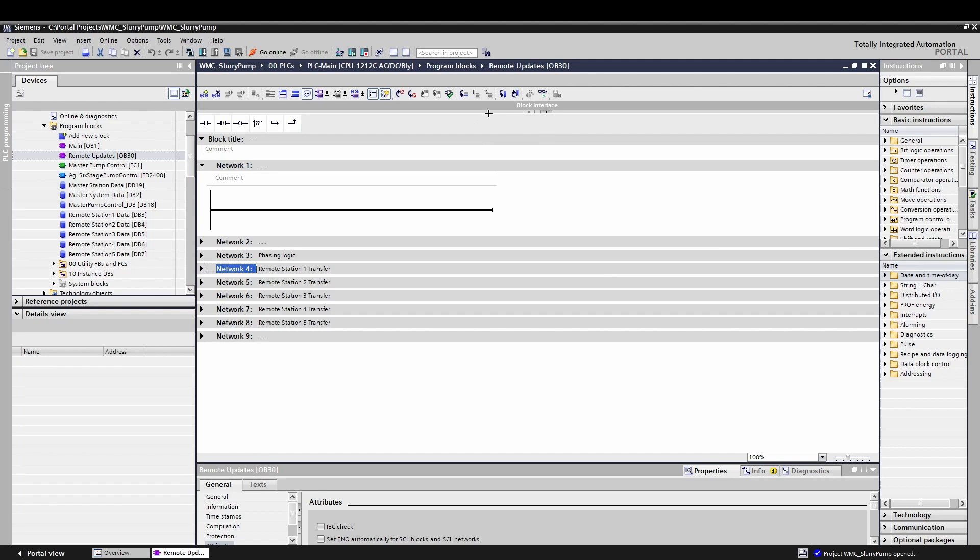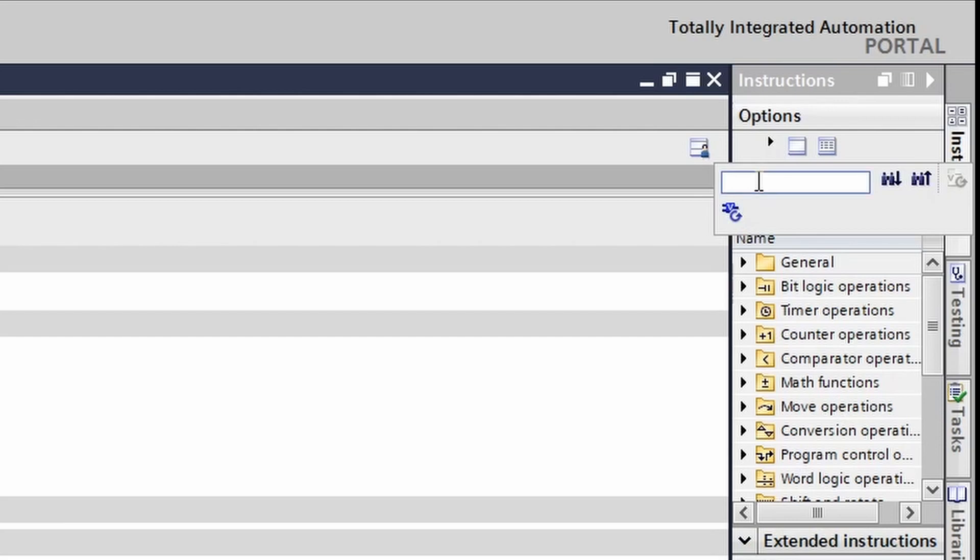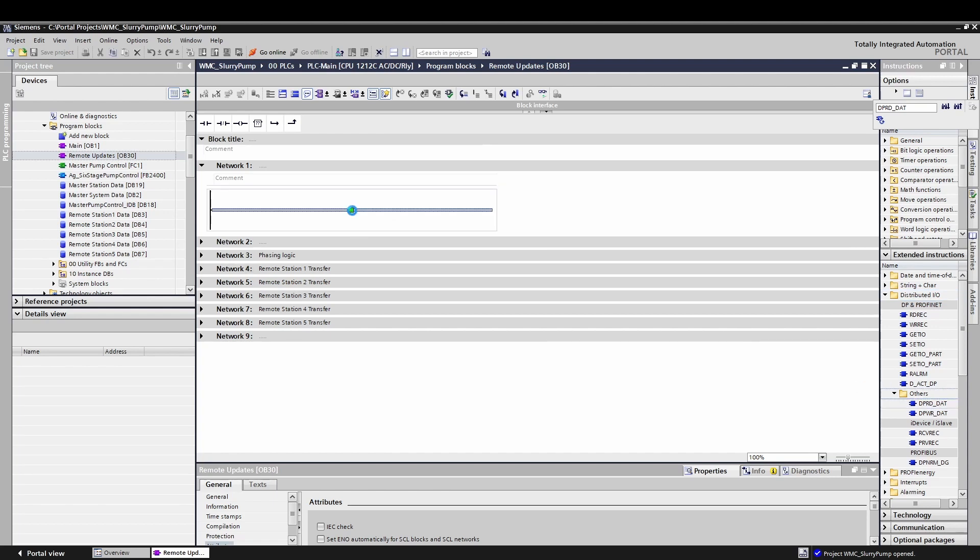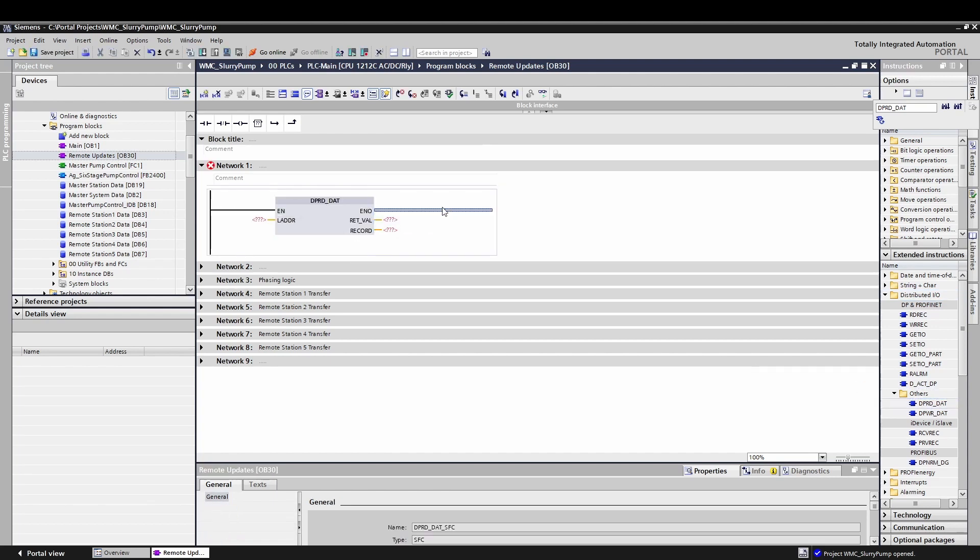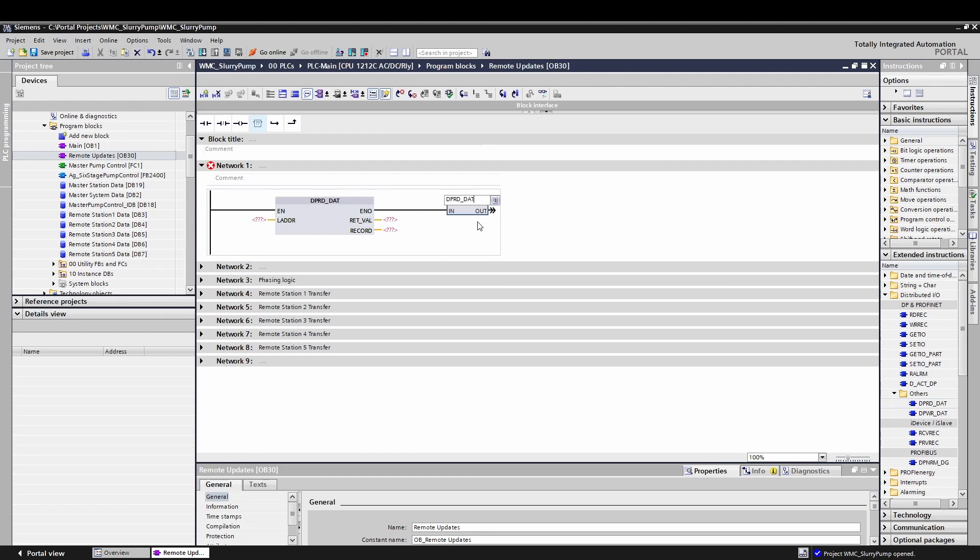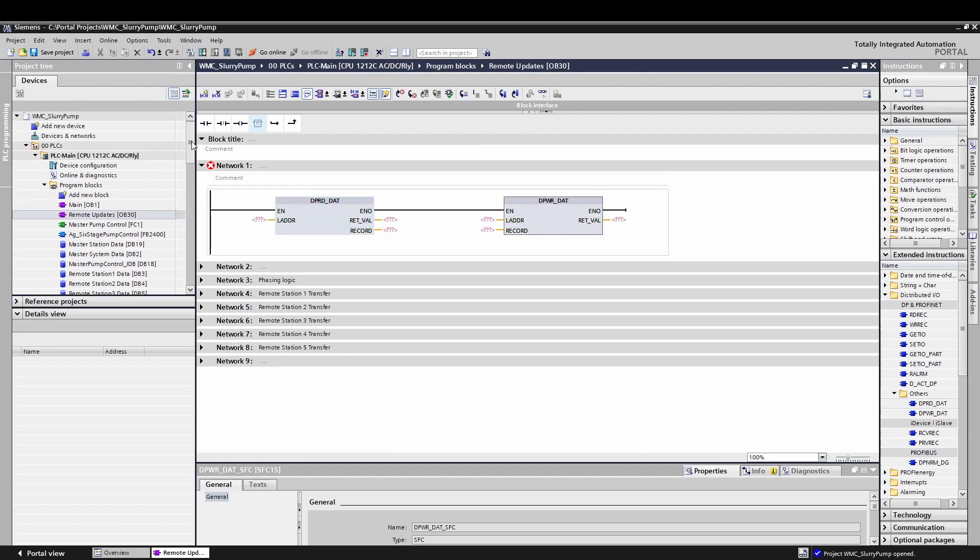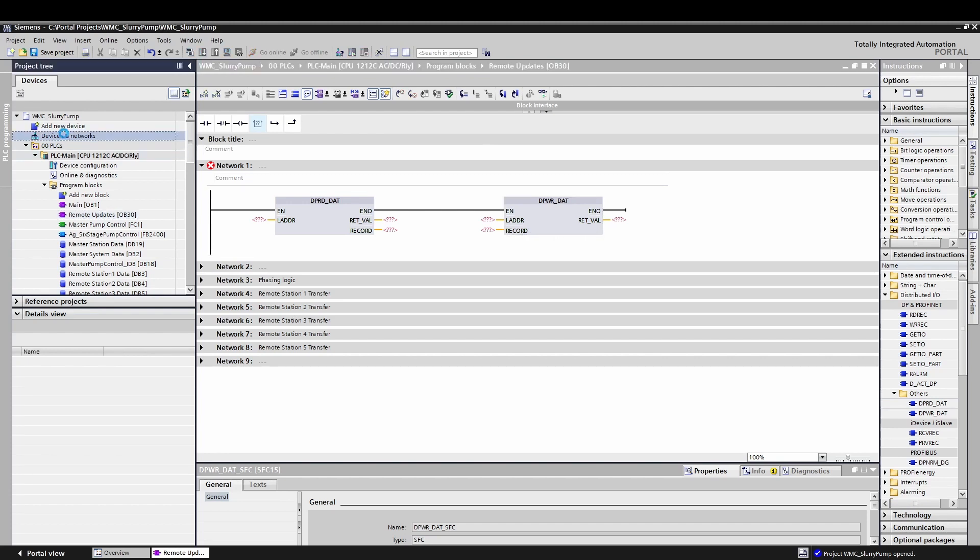I'll be discussing primarily the usage from TIA Portal, and I will highlight the one major difference in the software when it comes up. To find these blocks in Portal, go to your instruction tab in a ladder block and either search in the search box for dp rd underscore dat or navigate to extended functions, distributed IO, others. Drag the block onto a rung to import the code. Alternatively, you can always insert a blank instruction block and type dp rd underscore dat and press enter, and it'll import the code just the same. These blocks look fairly simple, and other than an error code output, they only use an address of the device you're connecting to and a record parameter.